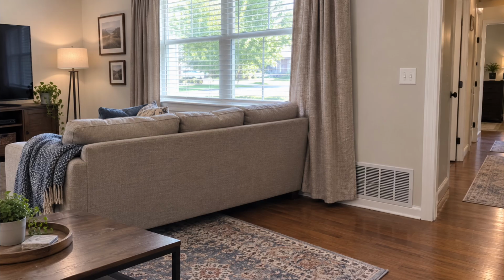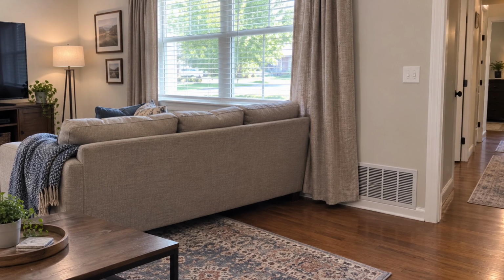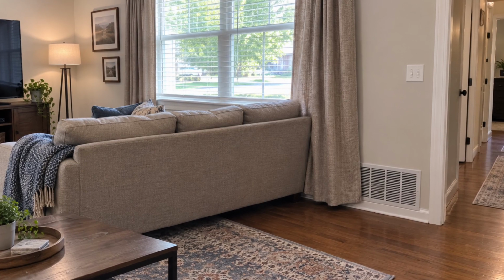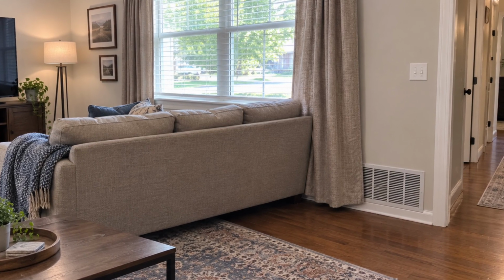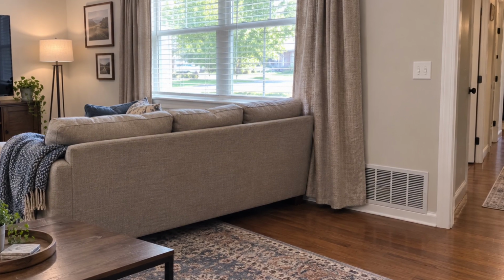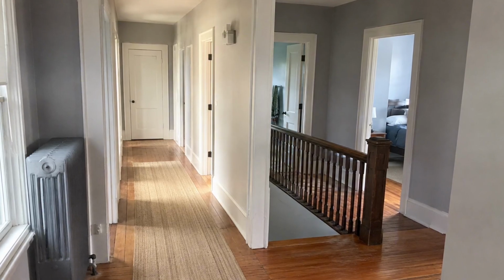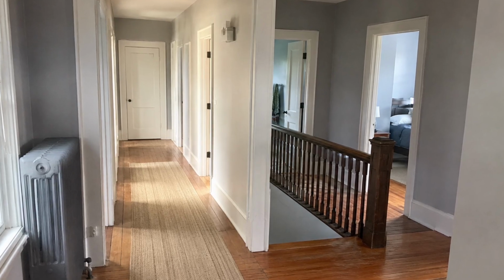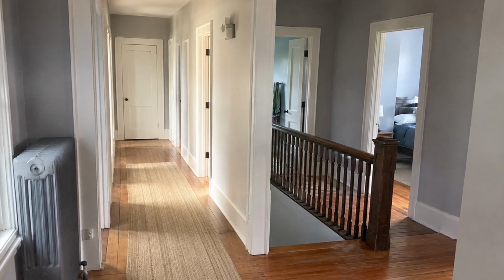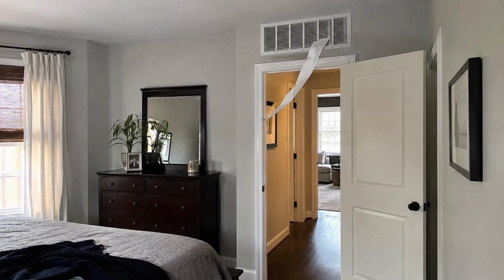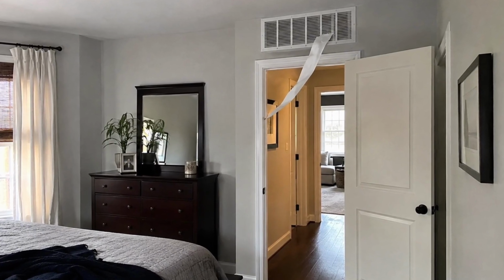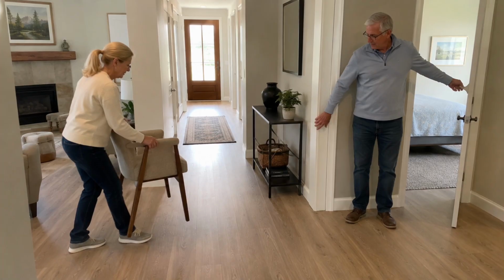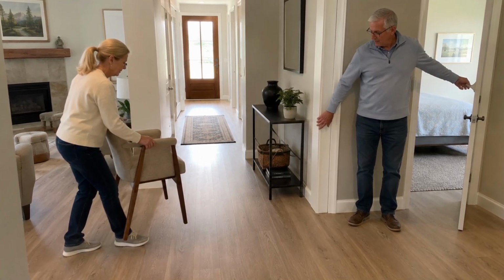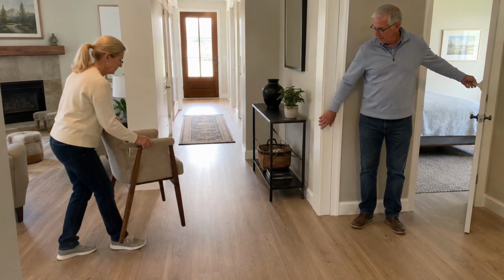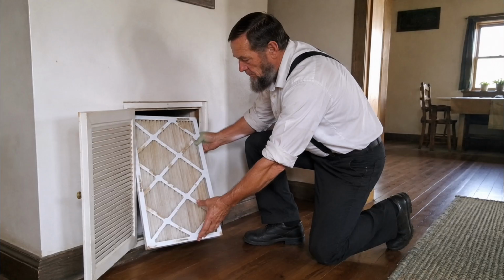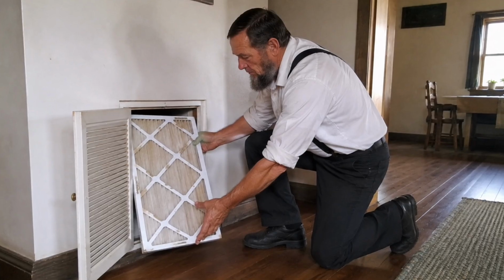Returns get blocked innocently all the time. A bookcase is moved in front of a wall grill. A couch is backed against one. Heavy curtains hang across it. In a house with one central return in the hallway, a bedroom door shut tight all day can also restrict the path back from that room. A room with its own return, a transfer grill, or another designed return path may behave differently. The practical check is simple. Expose the whole face of every return grill and do not assume a closed interior door is harmless when the room has no clear path back. Third, the filter.